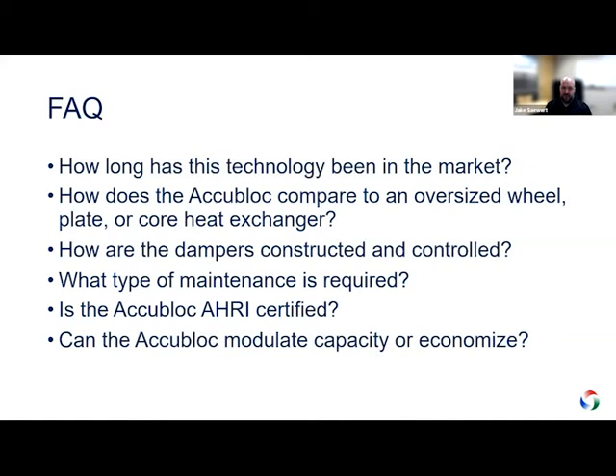If we're talking about face area for efficiency, can't I just make a wheel or a plate do that and just keep ratcheting up how much surface area I have? You can, but there's a diminishing return. We've done a number of different trials where we've compared the two, and you really start to max out on an enthalpy wheel at like 85%, and that's a huge wheel. Your velocity gets really low and it just becomes difficult to control. So it's just not really a feasible solution.